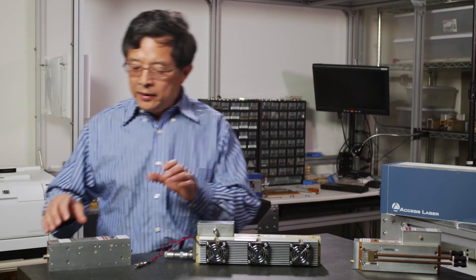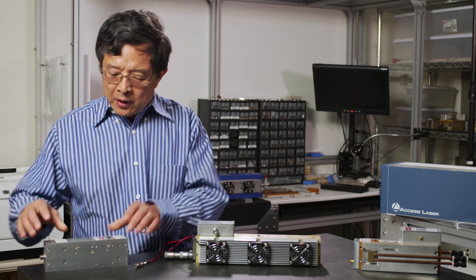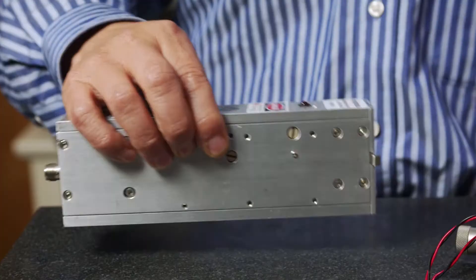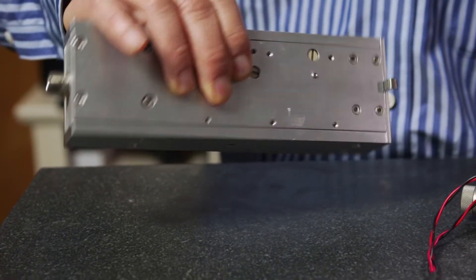Here at Access Laser, we offer three different configurations of cooling. One is the free air cooling, which relies on free convection and radiation to dissipate the heat. This one has the advantage of being portable, simple, no frills, and easy to operate.